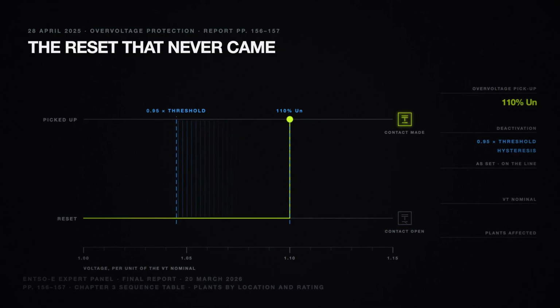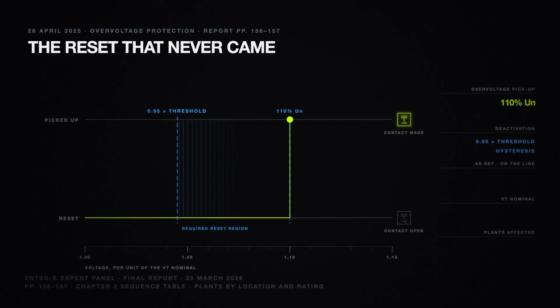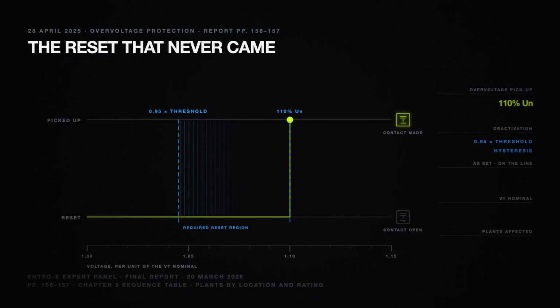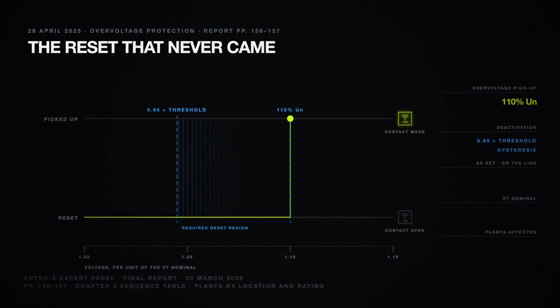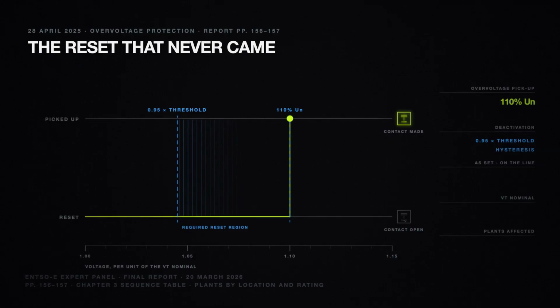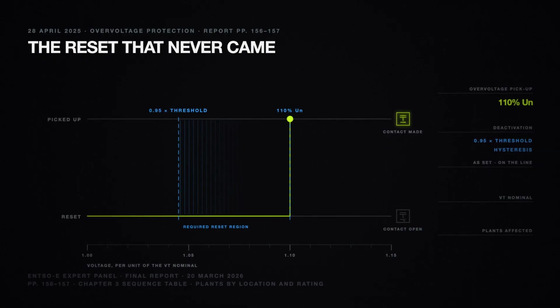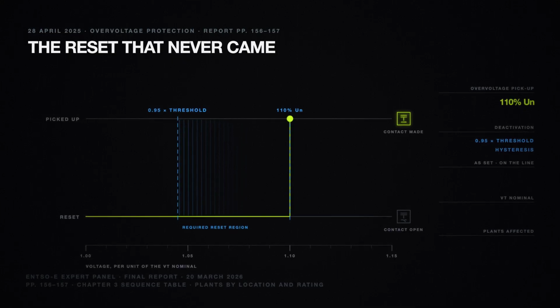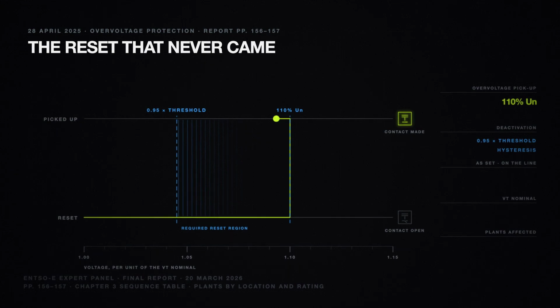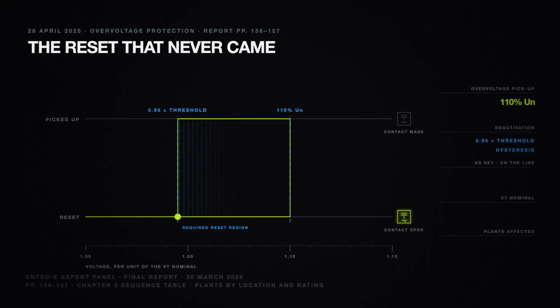The report puts it on pages 156 and 157. Even though the thresholds are set above the required values, the hysteresis associated with the deactivation of the overvoltage function, 0.95 times the voltage threshold, prevents the requirements from being fulfilled. A device set generously still fails the requirement, not because of where it trips, but because of where it lets go.